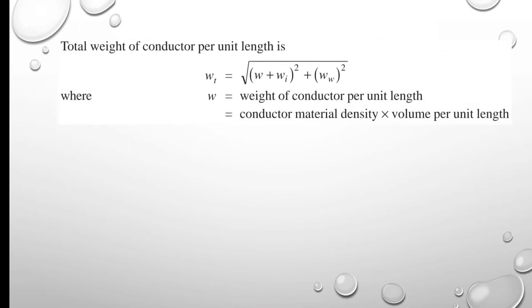The total weight of the conductor per unit length is Wt = √[(W + Wi)² + Ww²], where W is the weight of the conductor per unit length, equal to conductor material density times volume per unit length.